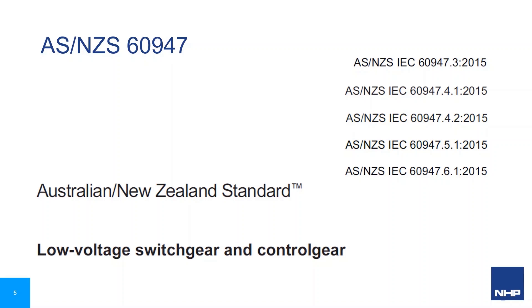These are covered in their respective standards for low voltage switchgear — IEC 60947 parts 3, 4, 5, and 6. The test requirements in these standards define the test parameters for the individual utilisation categories, with the required making and breaking capacity for each item of switchgear defined. Manufacturers are obliged to test according to these standards, which ensures the suitability of the tested devices for the respective application and enables comparison of products.